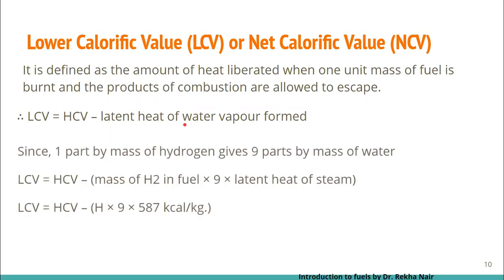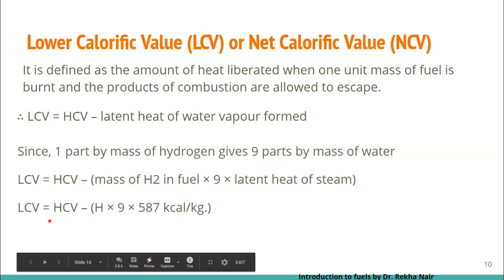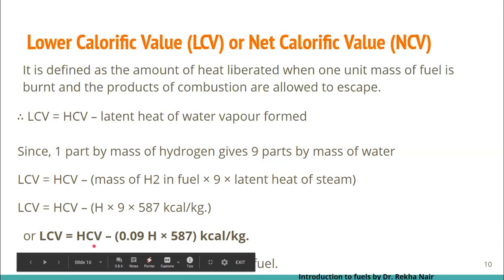Since one part by mass of hydrogen gives nine parts by mass of water, the latent heat of water vapor formed is: mass of hydrogen in the fuel multiplied by 9, multiplied by the latent heat of steam. So LCV = HCV − (H × 9 × 587), or LCV = HCV − (0.09H × 587), where H is the percentage of hydrogen.